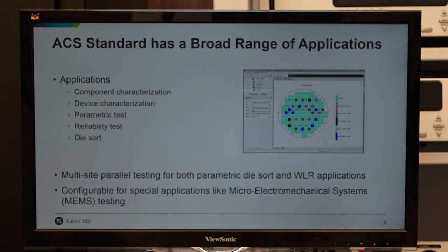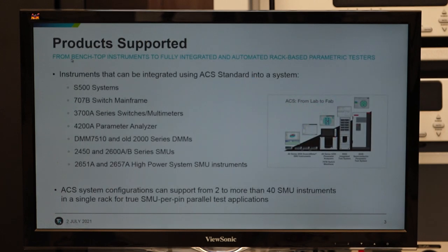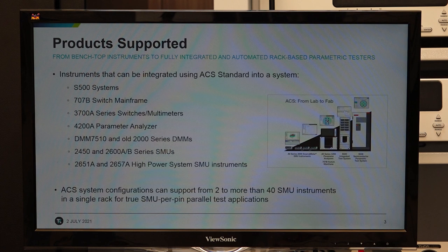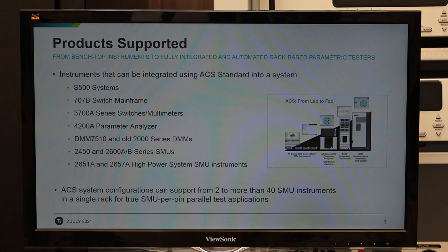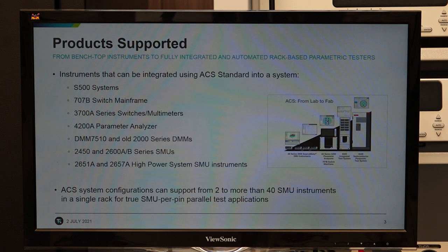ACS has a broad range of applications from testing individual components and packaged discrete components to device characterization, parametric tests for family of curves for each component, reliability tests, and DieSort or WaferSort applications found in process and monitoring. The ACS software allows configuring multi-site parallel testing for parametric DieSort and wafer-level applications. Products supported range from standalone bench instruments up to stacked and racked instruments to a complete process system called System 500, supporting from single-channel 2636 or 2635 instruments to multiples interconnected using TSP link, or working with the 4200.